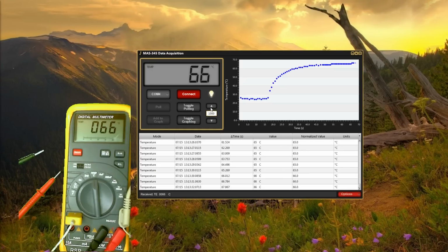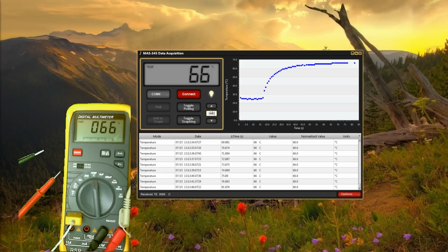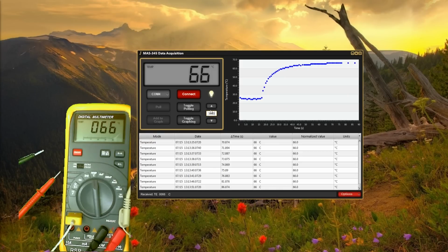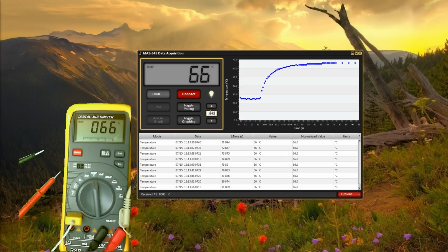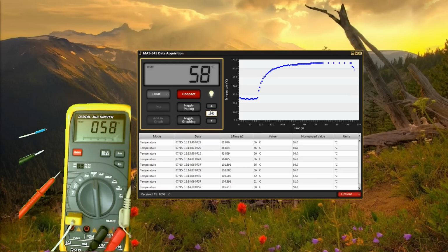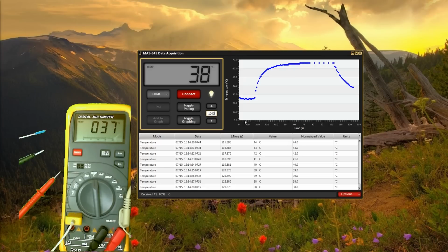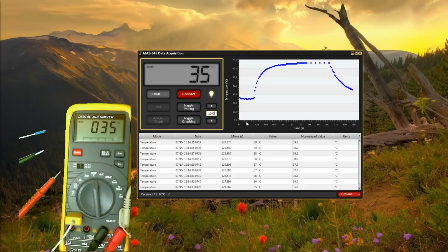But here we're changing the polling rate. Default is 1 second. It's measured in milliseconds though, so we have the default's 1,000. Here we've changed it to 5,000, so we're only polling the meter once every 5 seconds. It's best not to set the polling period lower than 1 second. If you do, the meter really bogs down, a lot of the controls on the meter become unresponsive, and the values you get won't be spaced by an even time differential. And that's just because the baud rate on the device is only like 600, so it just can't keep up.